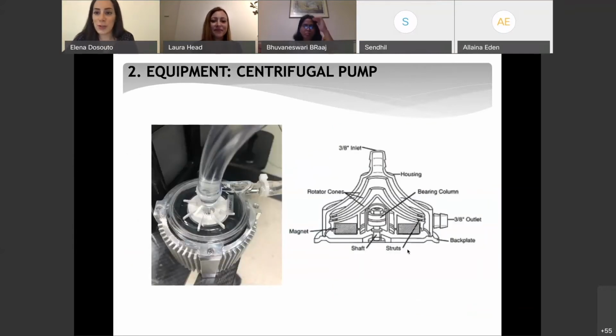So again, I'm really sorry to start with this, but let's talk about centrifugal pumps. Here you can see our CentriMag pump, which has a priming volume of about 30 mLs, and we are able to achieve up to 10 liters-ish a minute. A centrifugal pump consists of an impeller arranged with a nest of smooth plastic cones inside a plastic housing. The impeller couples magnetically with an electric motor, which is this metal bit in here. So the magnet inside the disposable pump head spins in conjunction with another magnet spinning in the driving console.